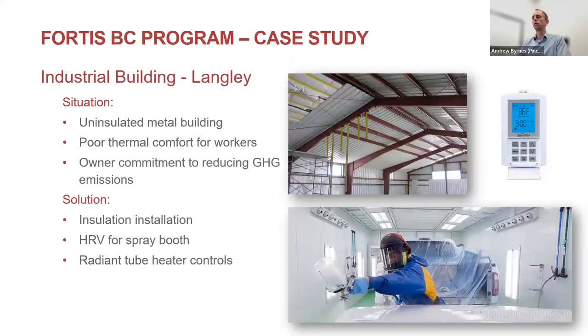Another case study - this was a Fortis funded project, an industrial building in Langley, a fabrication shop. They had an uninsulated metal building, or very little insulation, which caused poor thermal comfort for workers in the cold environment. The owner was committed to reducing greenhouse gas emissions corporately. So we looked at a few energy conservation measures, including adding insulation to the metal building, better control of radiant tube heaters with new control upgrades, and providing an HRV for a spray booth that used a large amount of natural gas for preheating makeup air.